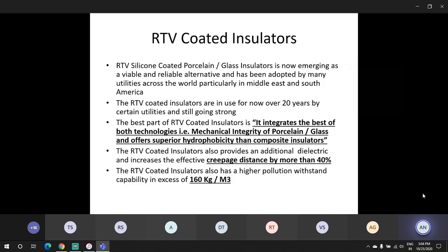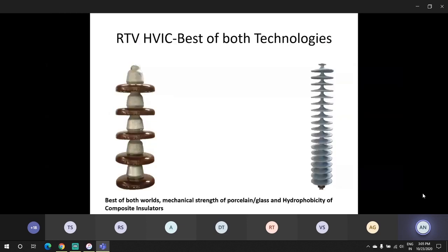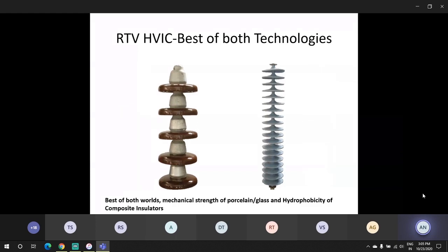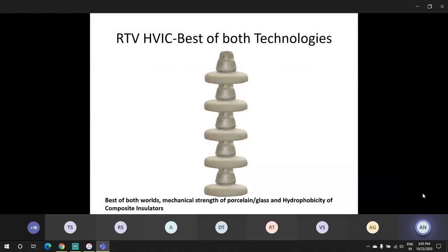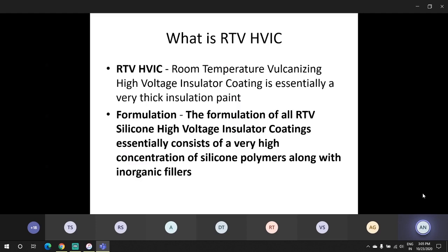This technology is now in use for more than 20 years by many utilities across the world. The best part of RTV coating is that it integrates the best of both technologies: the mechanical integrity of the porcelain and superior hydrophobicity than the composite insulators. It also provides an additional dielectric and increases the effective creepage by more than 40%. RTV coated insulators have a higher pollution withstand capability in excess of 160 kg per meter cube. If I make a pictorial representation, it is the best of both the technologies. That means the silicon is coated over porcelain or glass insulators, and it gives you the mechanical integrity of the porcelain or glass and the hydrophobicity of composite insulators.